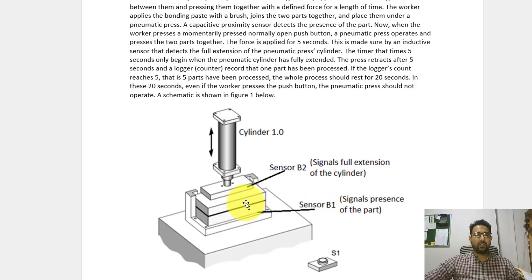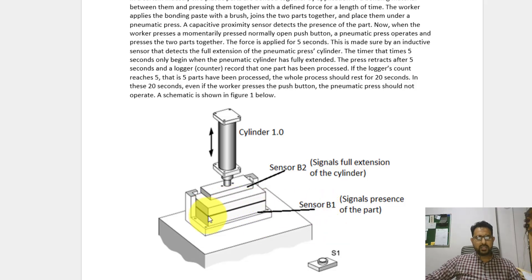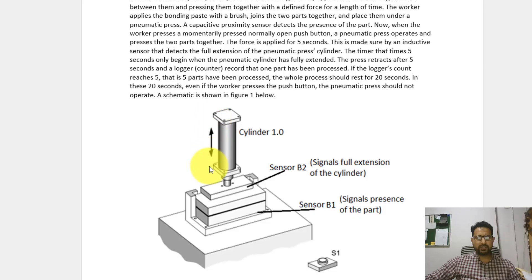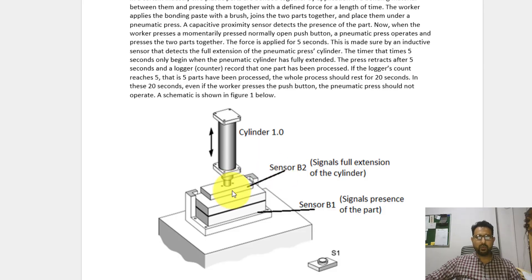Sensor B1 senses the presence of the part. Once the part is present and the worker momentarily presses the non-latching push button labeled S1, the pneumatic press will force the two parts together. We want this force applied for five seconds. Extension sensor B2 tells us whether the cylinder has fully extended. Once extended, a timer runs for five seconds, then the cylinder retracts and we count this as one cycle.